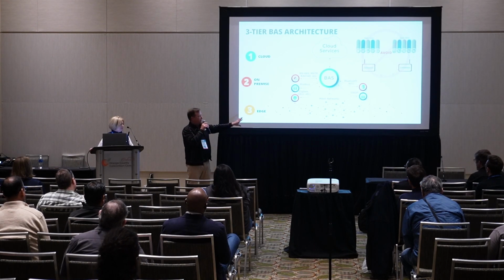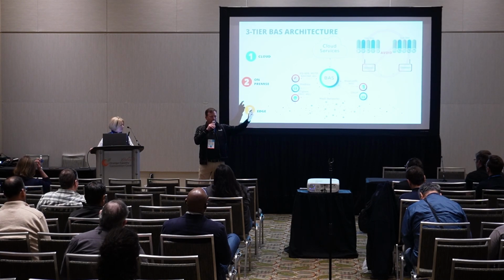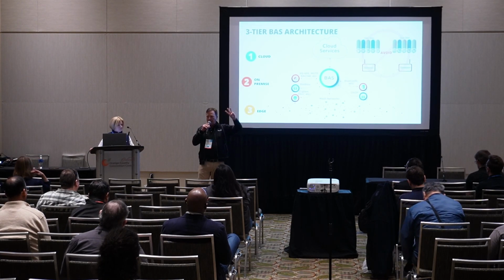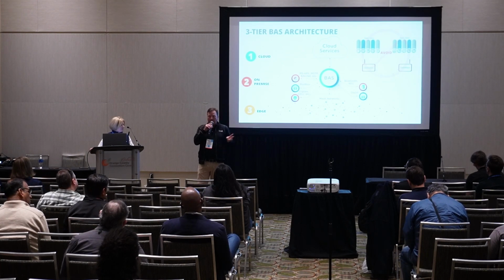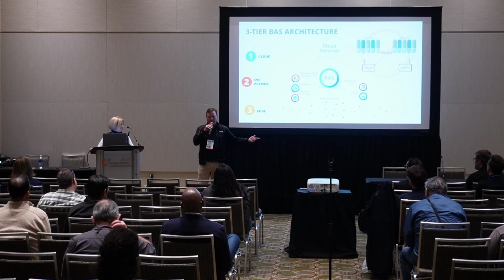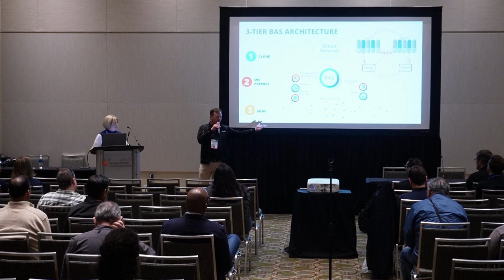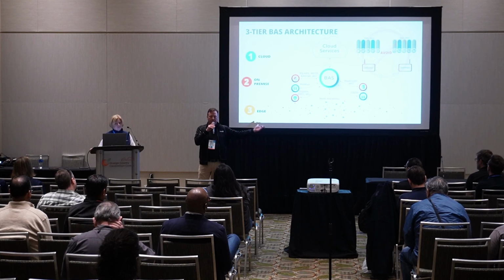Going back to that sensor example, say I have a sensor that has a web server, BACnet IP, and BACnet MSTP on it for communications. As the BAS designer, if I already have a BACnet MSTP network running throughout the building and I just need to get the data from the sensor, I don't need it served as a web page. I'm just going to tie it into my BACnet network because it just makes sense.